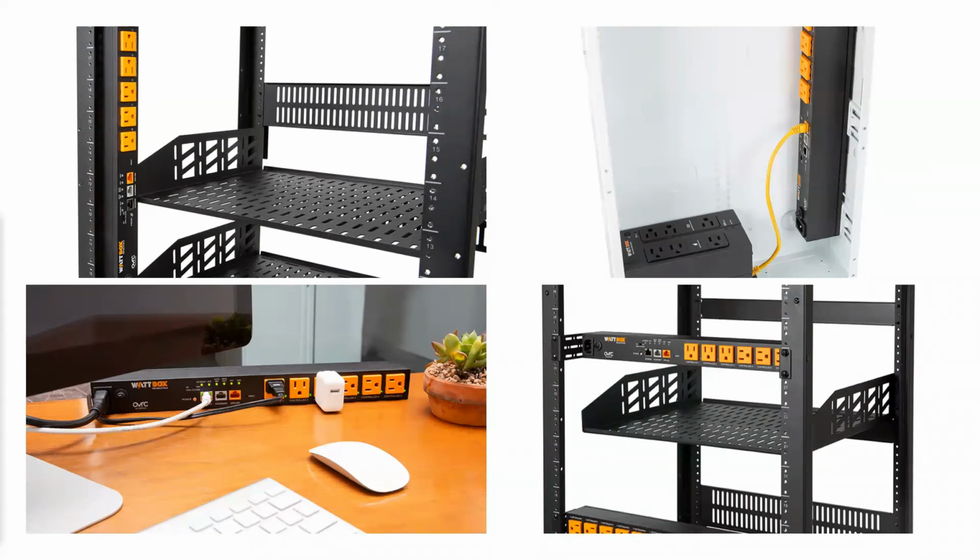Surge protection is typically what you would see in an MOV-based scenario, which means that when there is a surge event, an MOV essentially clamps down on that surge event, and it is self-sacrificing in that it takes the hit so that your devices down the line don't fail. With that being said, when a surge event occurs in a Wattbox, the Wattbox will fail because of that. Then you have surge suppression types of technologies, which are designed to suppress the surge, and the unit itself should still function after that surge event. We do not use that with our Wattbox products today. We are all surge protection, which uses the MOV-based technology within our solutions.